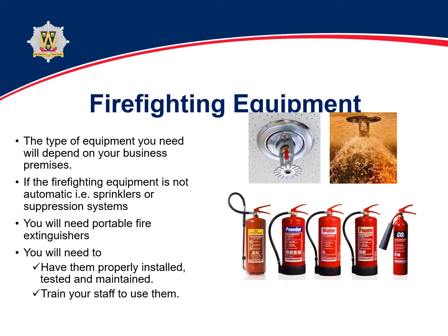Firefighting equipment then. So you need to have a way of fighting a small fire. If you don't have sprinklers in your premises, then portable firefighting equipment will be required. Sprinklers are only really put into very large open plan areas to control the fire size. But portable equipment will be required. Again, dependent on the size of your premise and the type of business carried out will determine the type of extinguisher for the risk.